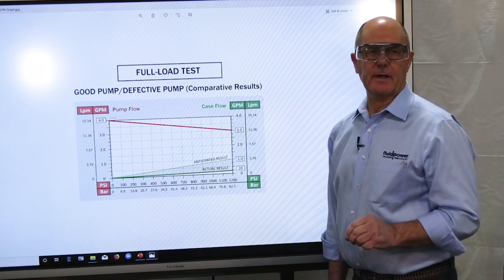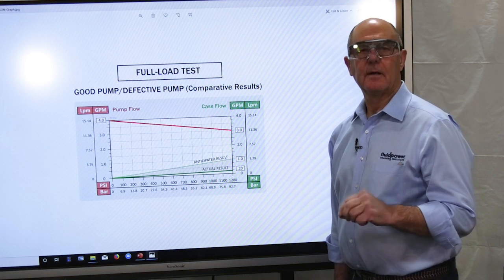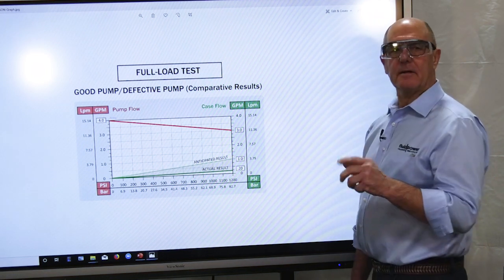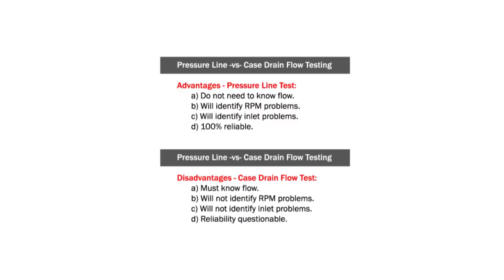Even if a pump case flow test were scientific, I would opt for a pressure line test over a case flow test. With a pressure line test, I do not need to know the pump's rated flow — if I have a 10 GPM pump and I lose 2 gallons per minute, I know that is 20% at load. However, on a case flow test, if I have 2 gallons per minute coming out of the case drain line and I don't know the pump's rated flow, that number is unknown and therefore meaningless.